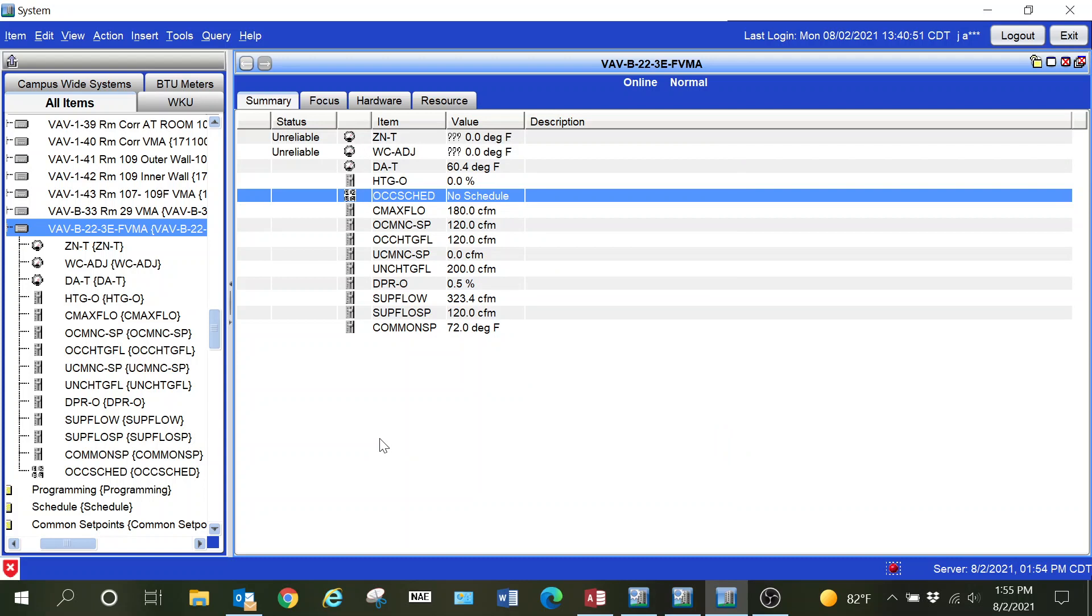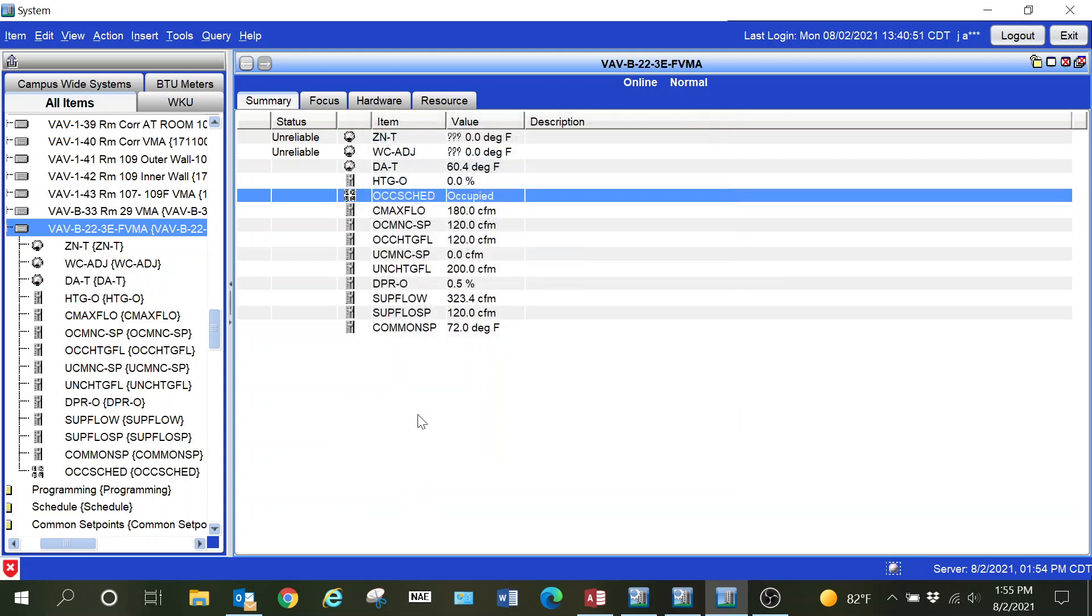You see the zone temp and warmer cooler adjust on this is currently offline. We had to replace the thermostat as well and had not gotten that done at this point. That is another thing that you want to note when you do this pulling in those points with PRN file.